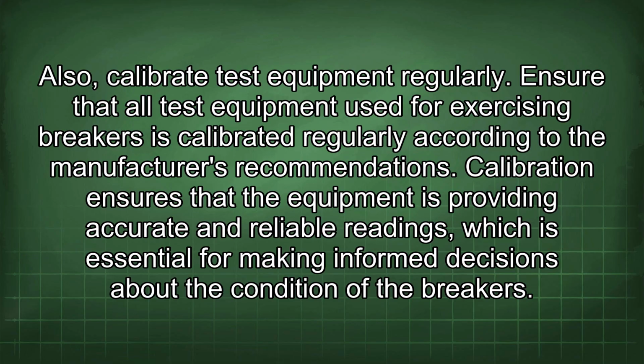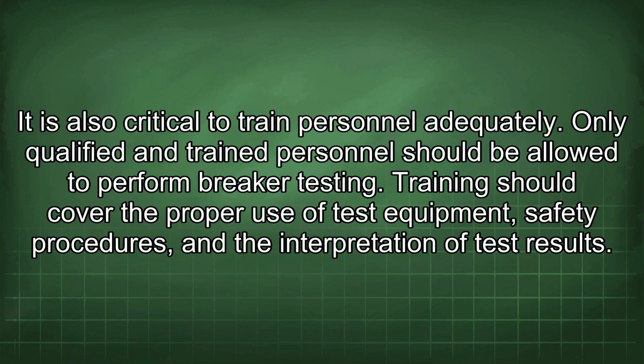Ensure that all test equipment used for exercising breakers is calibrated regularly according to the manufacturer's recommendations. Calibration ensures that the equipment is providing accurate and reliable readings, which is essential for making informed decisions about the condition of the breakers. It is also critical to train personnel adequately.